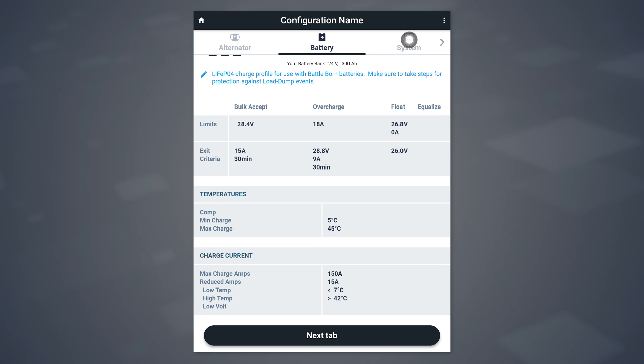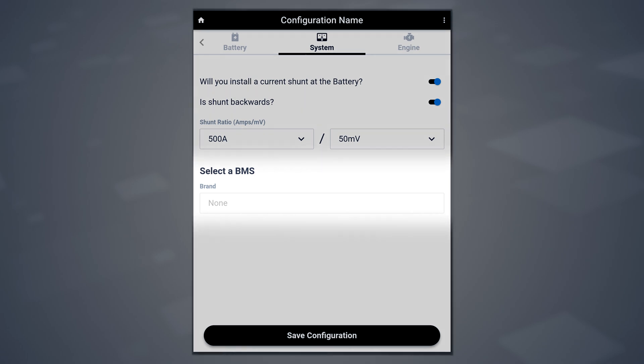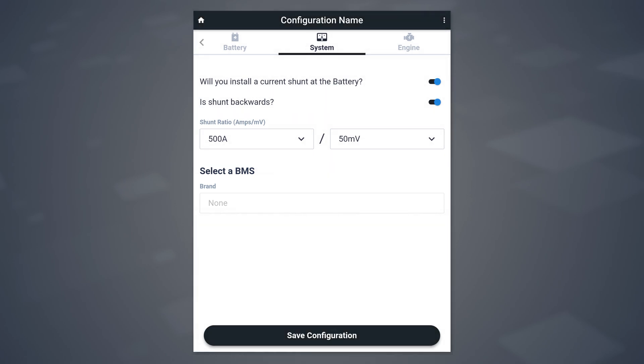We'll now proceed to the next tab, System. Here, you can define things such as whether you have a shunt — and yes, I want to have a shunt. If you happen to wire it backwards, you can either change those wires or just toggle this to reverse it. You can also define what your shunt is; 500-amp, 50-millivolt is very common. In this case, there's no BMS available, as the Battle Born battery we selected has a built-in BMS, so that's why we're not able to select it at this point.